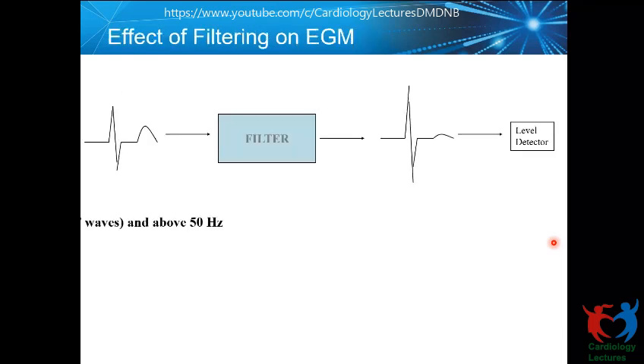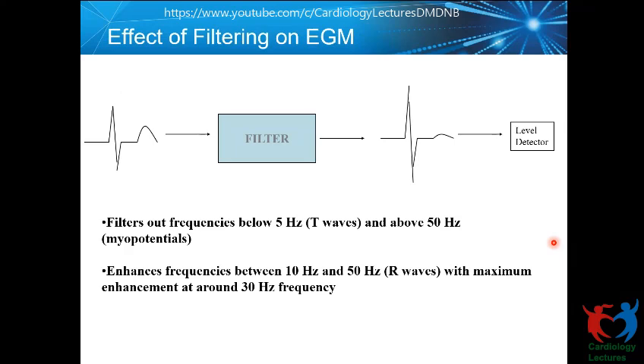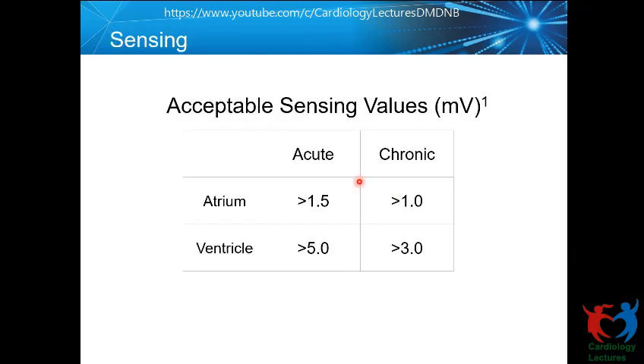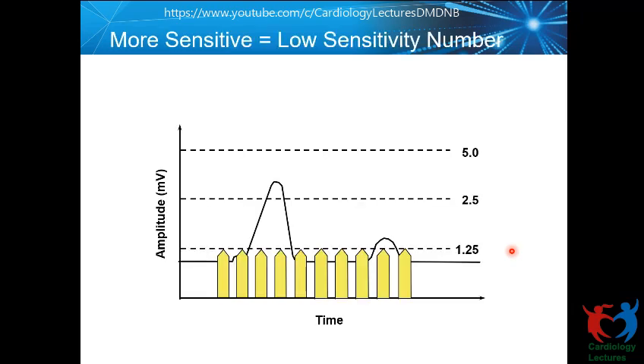And then, as I said, the electronics filters and amplifies this, and then that is put through the sense detector. That's where we program the sensitivity setting. Typically, you want to have in the ventricle an amplitude of 5 millivolts or more of R wave and 1.5 millivolts or more of P wave. And at follow-up, even 3 millivolts in the ventricle is an acceptable value. And you program a sensitivity setting. I'm sure you're familiar with that.